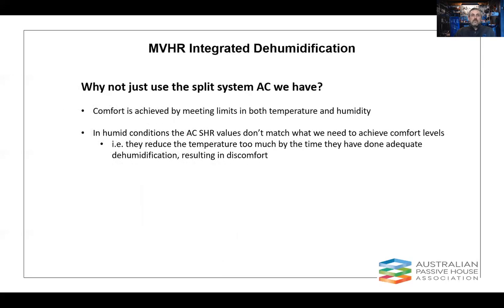So why not just use the split system AC? Now, we'll have a little look at what's called a psychrometric chart here to explain what comfort is, but intrinsically we all know comfort is a mix of both temperature and humidity. We've all been to Queensland or somewhere tropical, and whilst the temperature's been lovely, it's been a bit stuffy and sticky. And so that's sort of what we're talking about. The concept of an air conditioner SHR value or sensible heat ratio. And the next slide will give you a little bit of an idea of what that is. Doesn't often match what we need in high performance houses for more humid climates. And we're talking definitely Queensland here. We might be talking northern New South Wales, just depending on your specific locations.